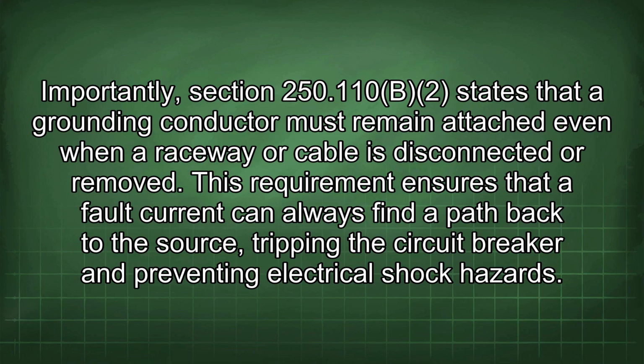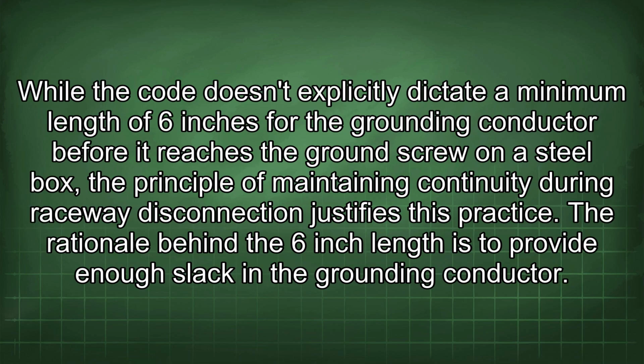This requirement ensures that a fault current can always find a path back to the source, tripping the circuit breaker and preventing electrical shock hazards. While the code doesn't explicitly dictate a minimum length of 6 inches for the grounding conductor before it reaches the ground screw on a steel box, the principle of maintaining continuity during raceway disconnection justifies this practice.